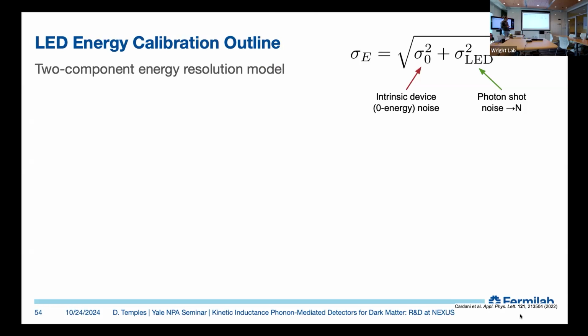Okay, so we did this LED energy calibration, which I will outline the recipe for before going into the data here. We pulse our LED onto the device with fixed voltage, and then we can sweep that voltage to change the optical power that's delivered. But for a particular setting, we expect a monoenergetic peak in our energy spectrum.